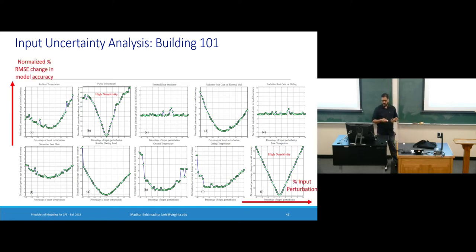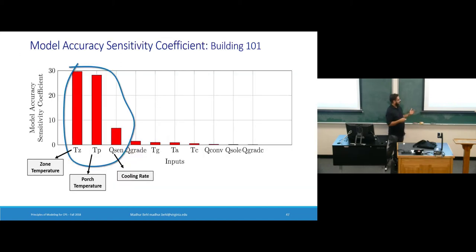This has the same x and y interpretation. For real data from that building, we see that zone temperature, porch temperature—not plenum, this is porch for that building—and the HVAC cooling load influence the model accuracy the most. So what we observe in simulation is consistent with how it works in the real world for an actual building.